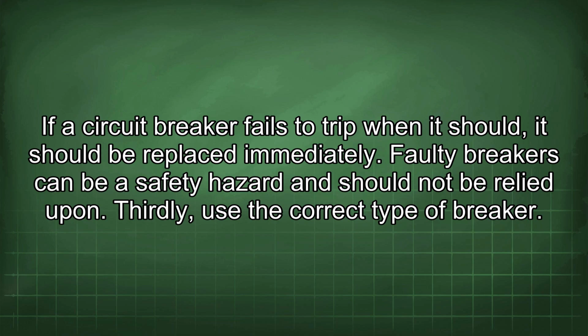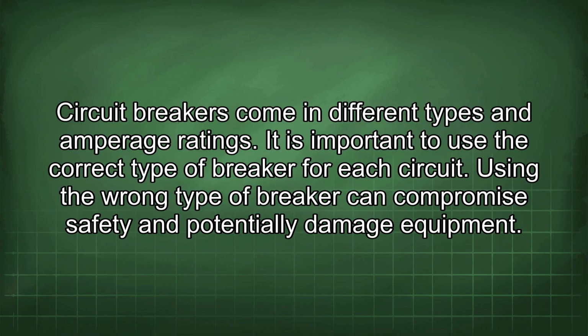Thirdly, use the correct type of breaker. Circuit breakers come in different types and amperage ratings. It is important to use the correct type of breaker for each circuit. Using the wrong type of breaker can compromise safety and potentially damage equipment.